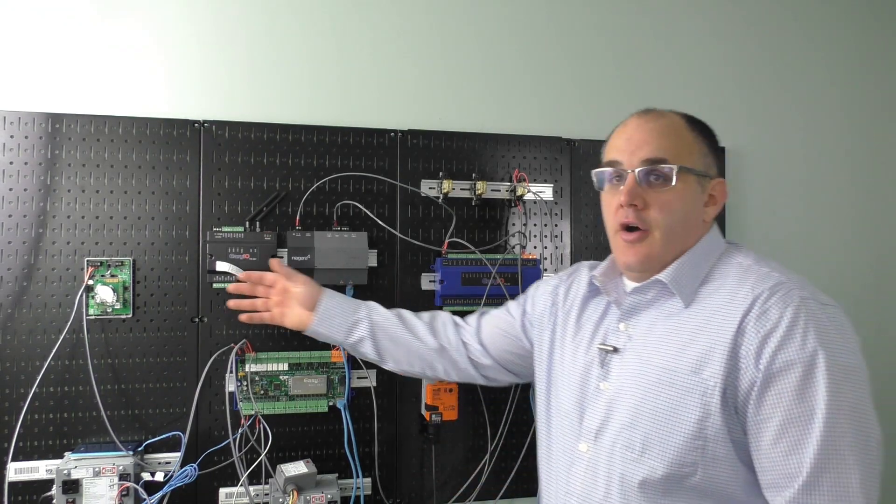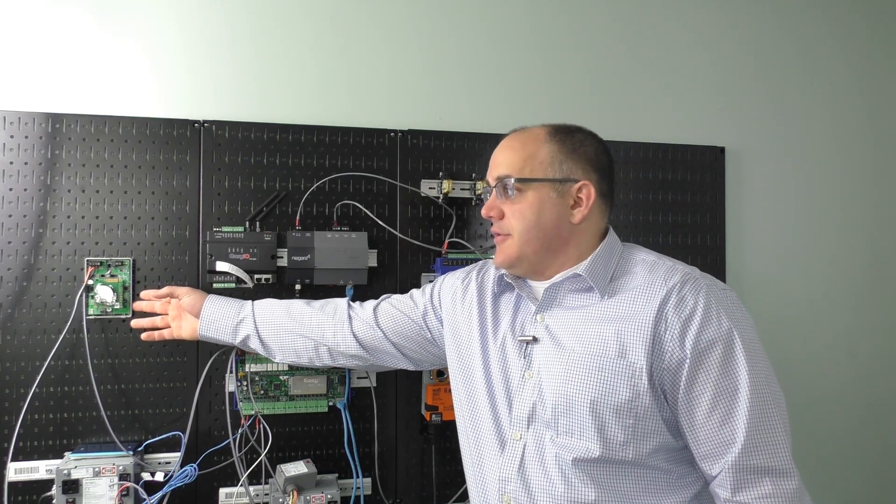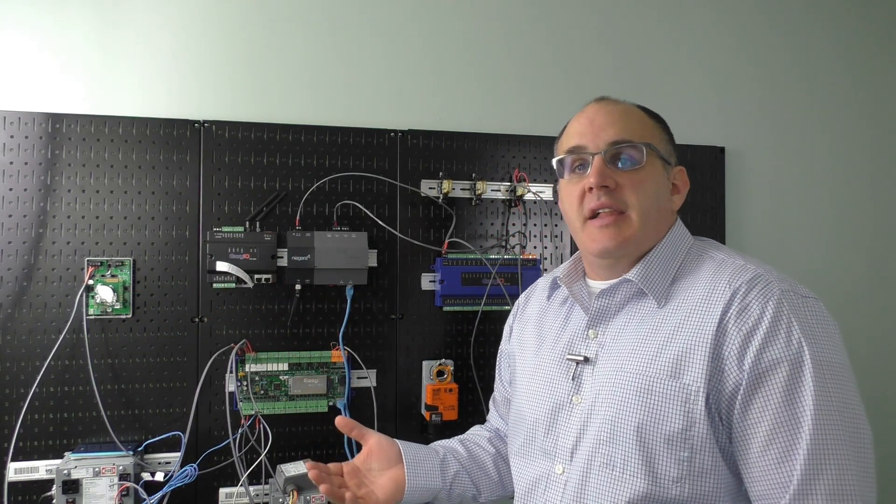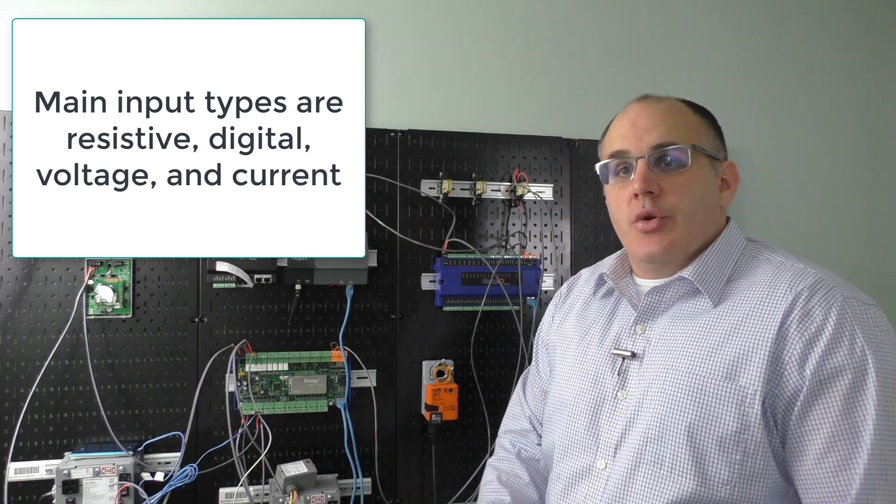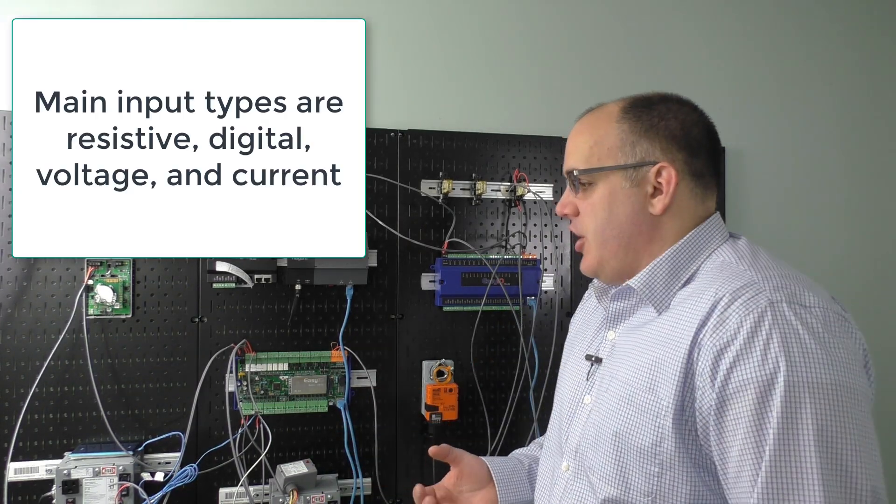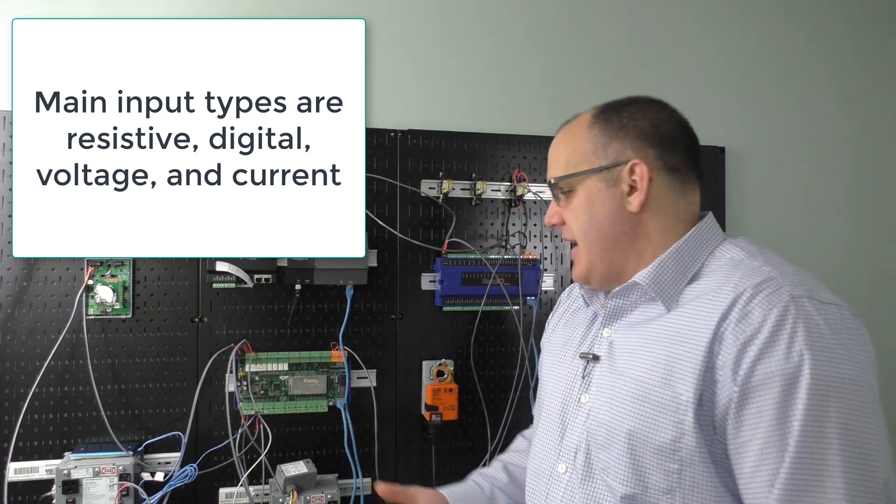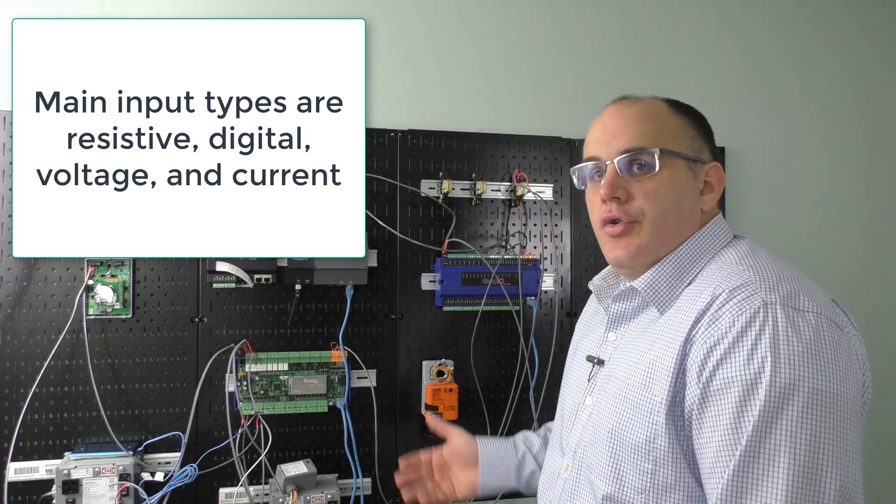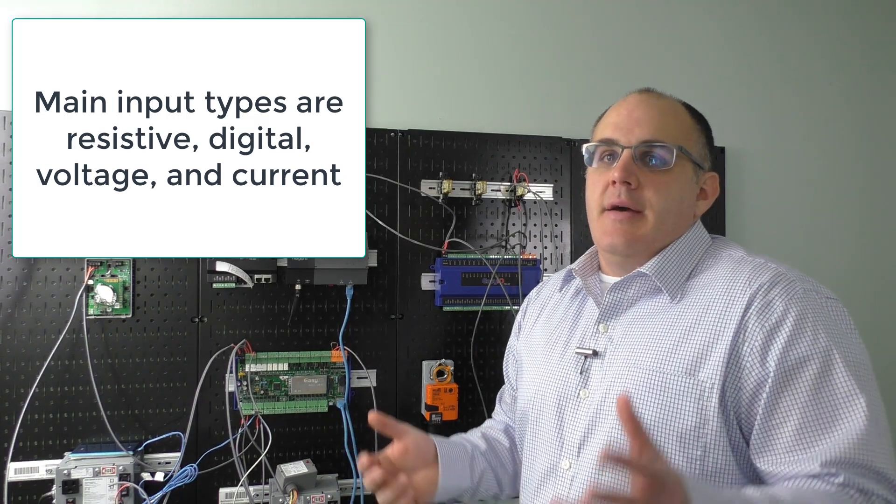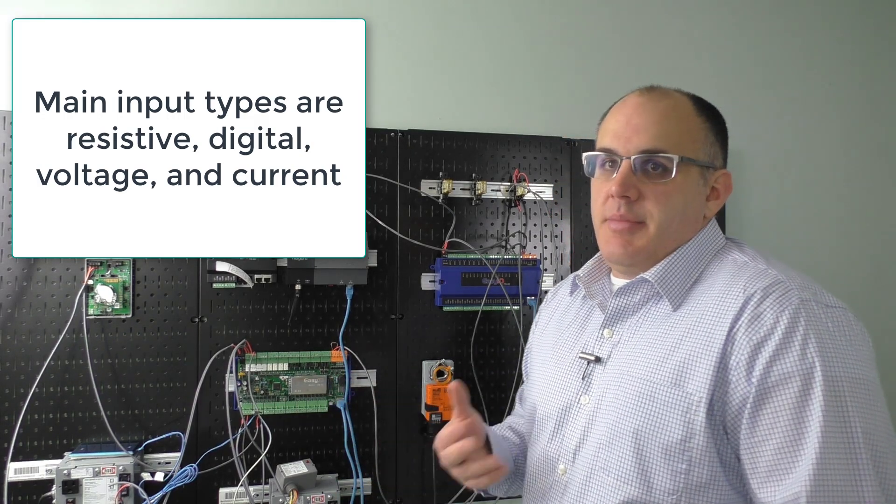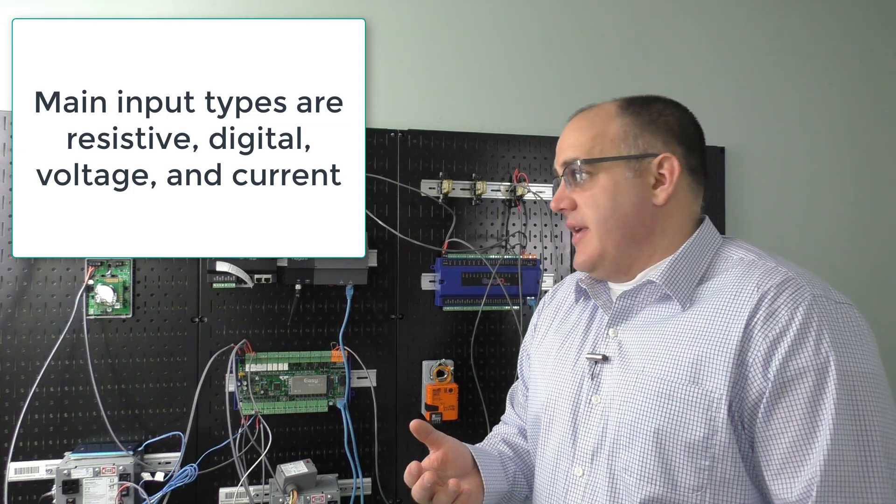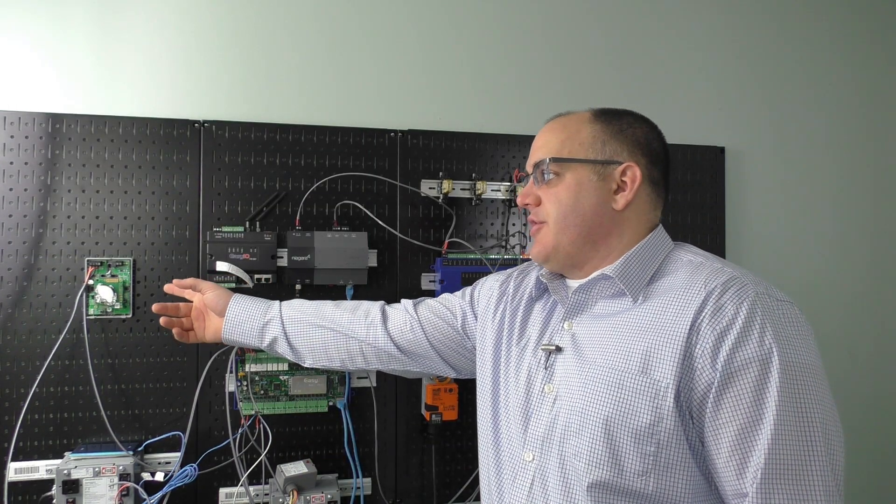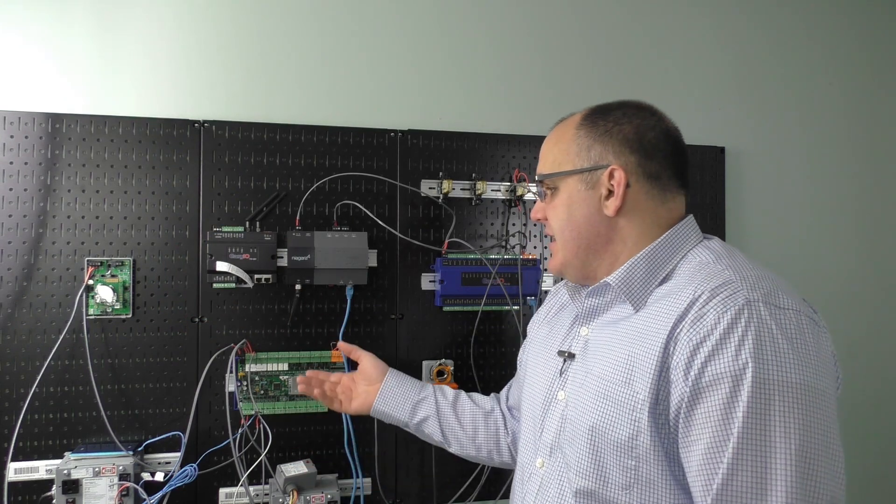For example, with this actuator over here, we have a status where a set of contacts close once this actuator gets to a specific position, and that gives us status that the actuator has met its specific position. Over here, we have a CO2 sensor. This CO2 sensor can give us 4 to 20 milliamp or 0 to 10. So we've just talked through several different input types: resistive input, contact or binary/digital input, and voltage.